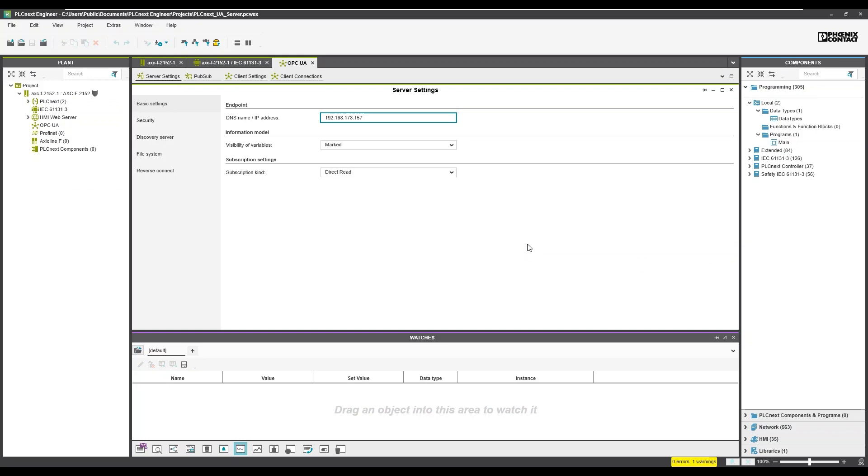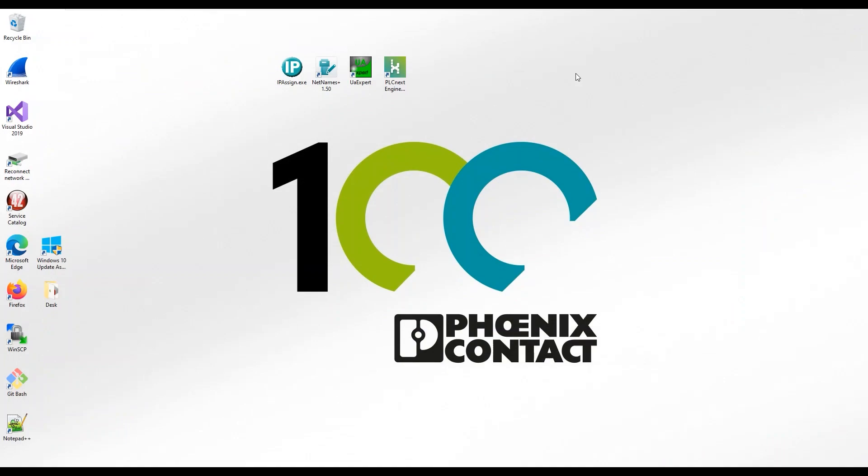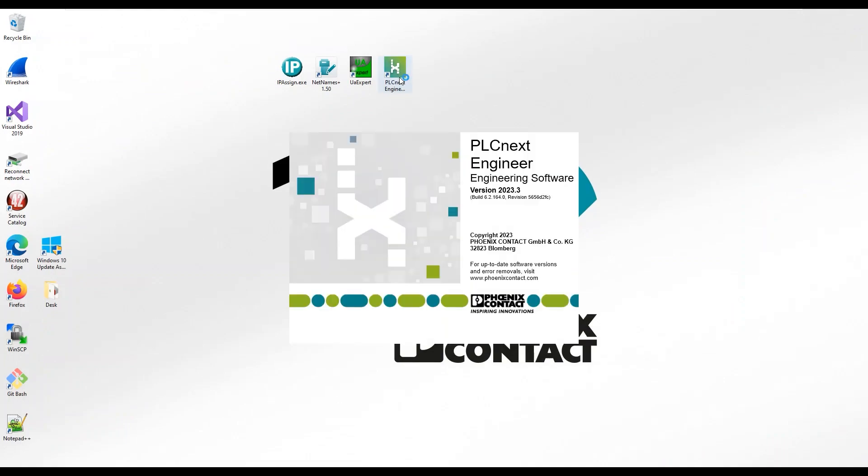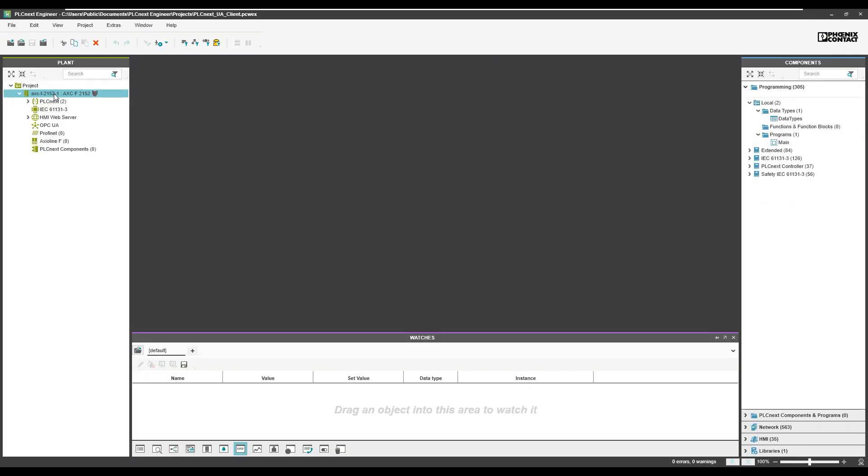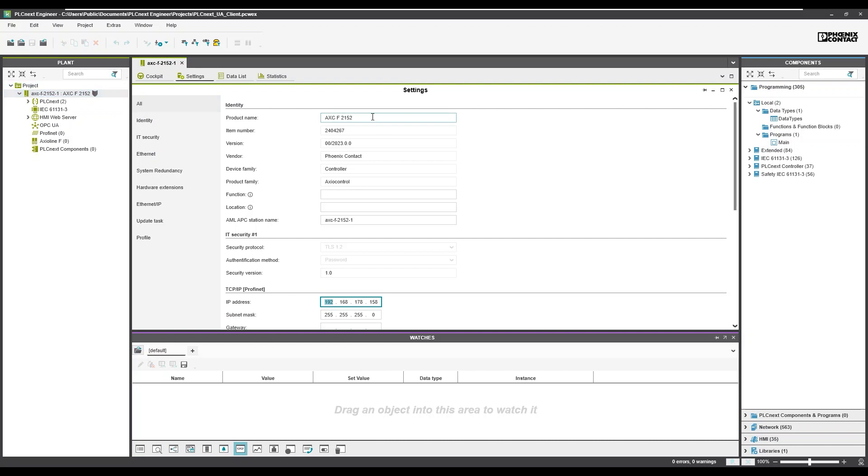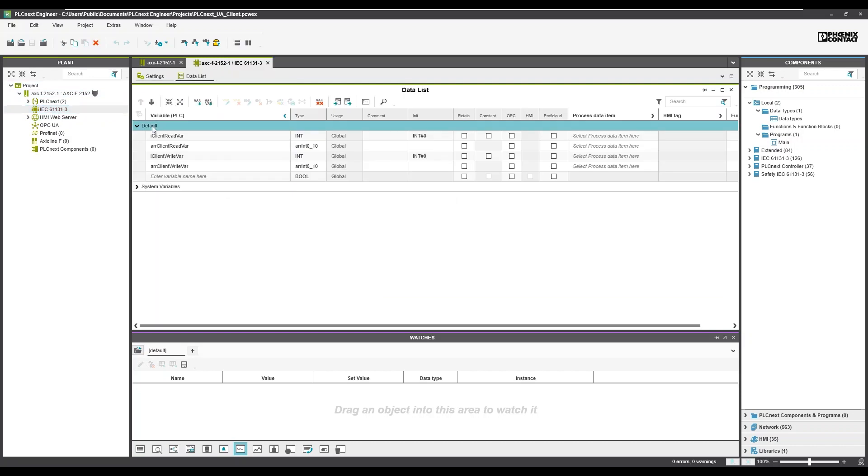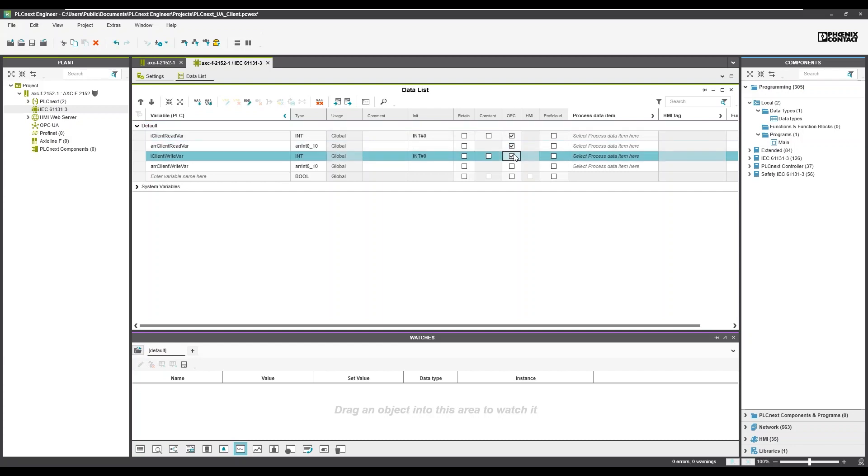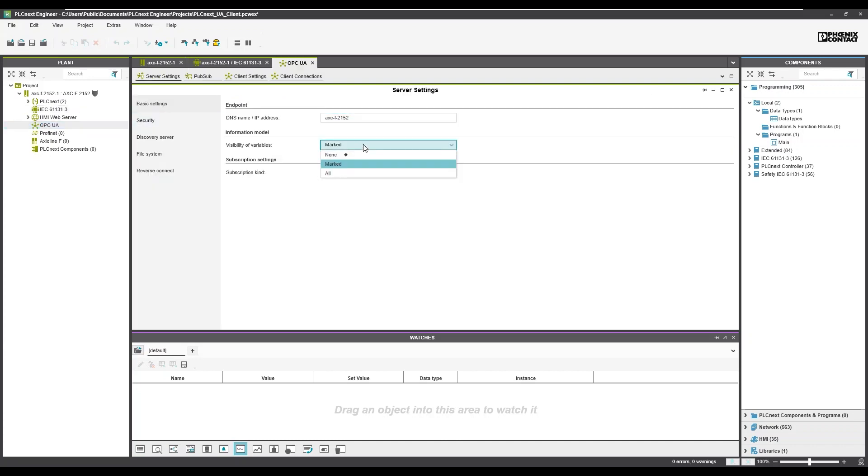Close the server project and open PLCnext Engineer once again. For the client, you have to use a version 2023.3 or higher. Also for the client, I already created a very simple application which is based on the 2152, as well as the template 2023.0. I have also here four variables which are the corresponding variables for the server, but here I renamed them. I named them for the client. There's the same data type, so integer as primitive type, and the array of integer for the field. We have to activate, as well on the client side, the OPC checkbox and activate that the marked variables are visible. Also here we have to consider the endpoints which are part of the certificate. As I will not use a DNS server or the DNS names, I have to enter also here the IP address of the client.